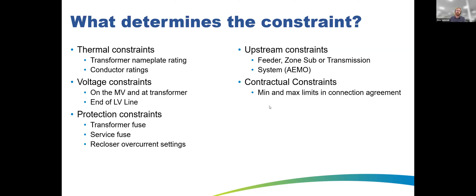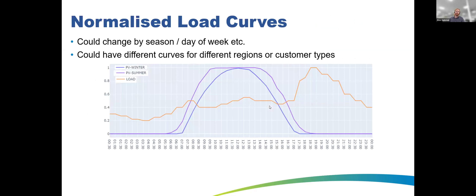We also have contractual constraints with the customer. When they sign up we offer a minimum–maximum limit, for example 1.5 to 10 kW. We can't go below 1.5 except in emergency situations, as that's the guarantee in the contract. For the scheduled basic method, we don't have real-time transformer power flow data. Profiles vary by season, day of week — weekdays, weekends, and public holidays differ — and by region. Queensland is a large state, so Cairns has a very different load profile to somewhere like Toowoomba.